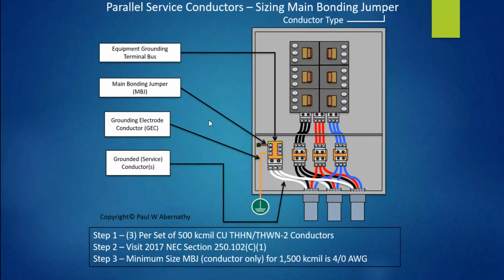So we wanted to give you that example here of the 3 raceways in parallel. And here it is. Step 1, 3 sets of 500s. This is kind of what it would look like. And if you go to 250.102(C)(1), it's going to say that here, this main bonding jumper, if this is not factory installed, then it's got to be sized based on here. So it would be 500, 500, 500, 1500.